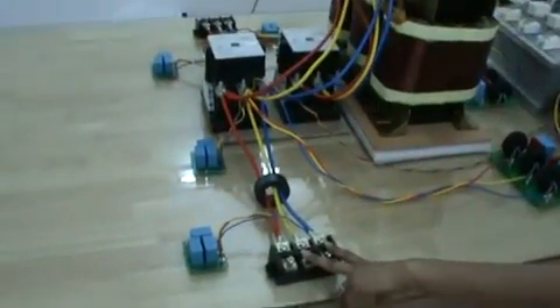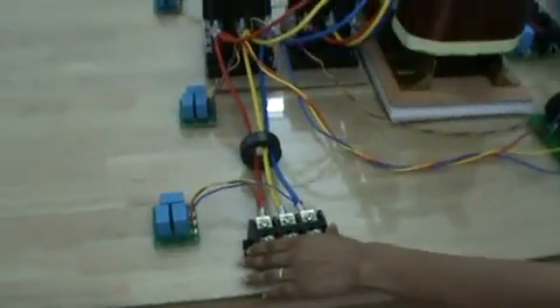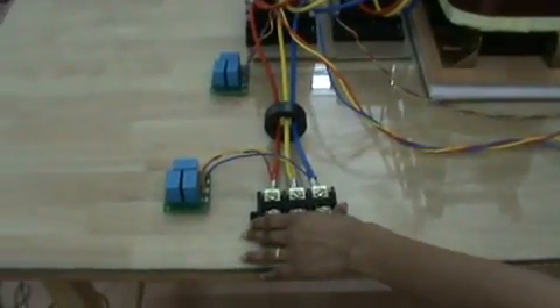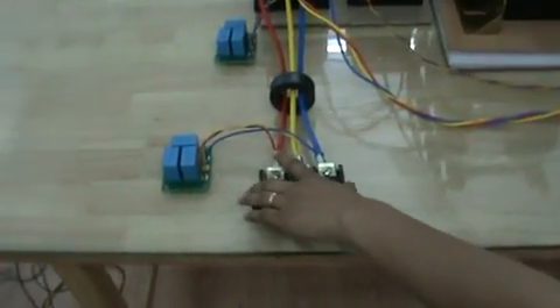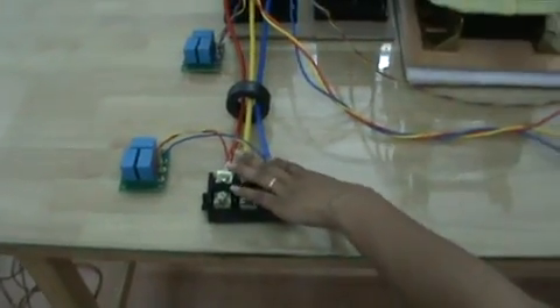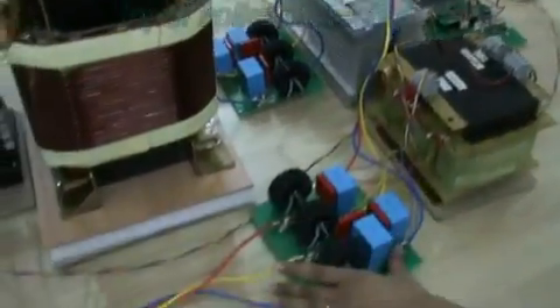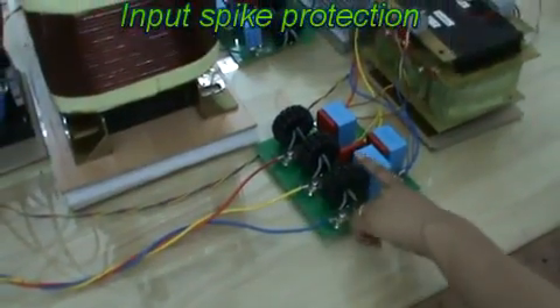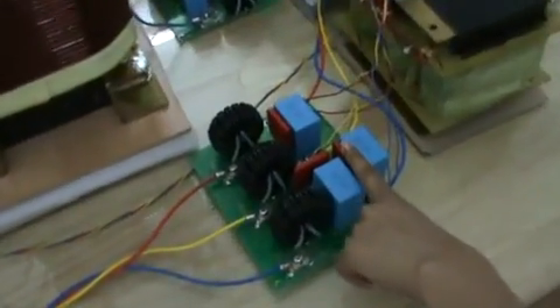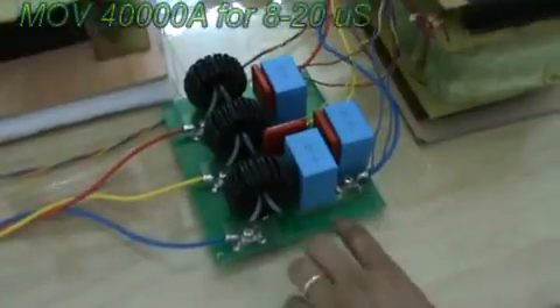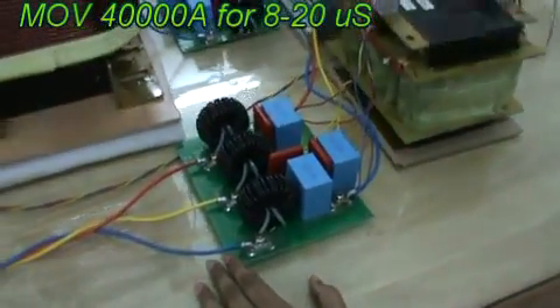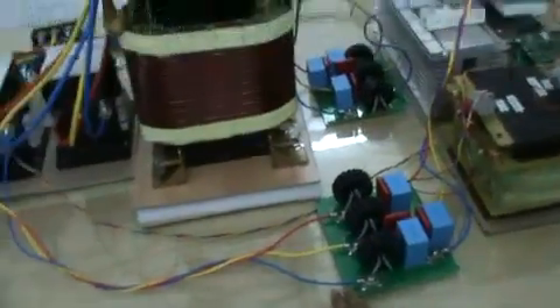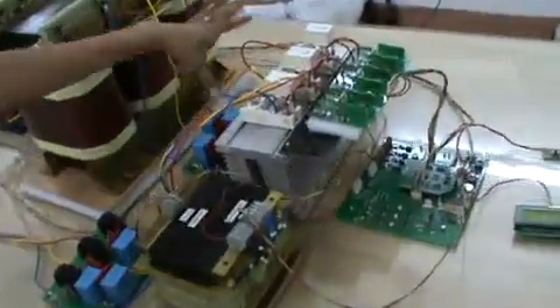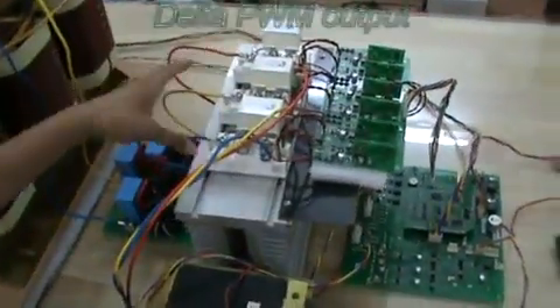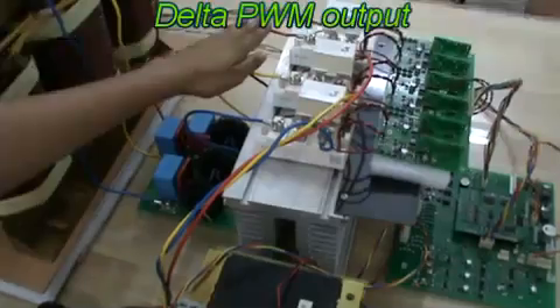This is the 3-wire input. The input range in delta VO is 381 volt to 433 volt. You can see the 3 wires R, Y, B. The input is going to the IGBT through a spike protection circuit. These MOVs will suppress any high voltage spike and can absorb maximum current of 40,000 ampere for about 8 to 20 microseconds. These are the IGBT modules, and here the PWM output will come.